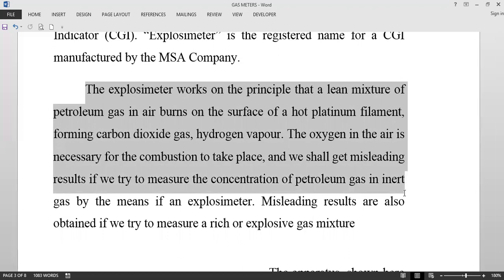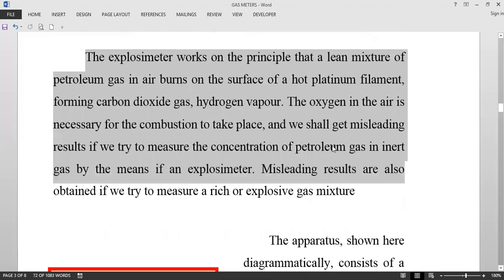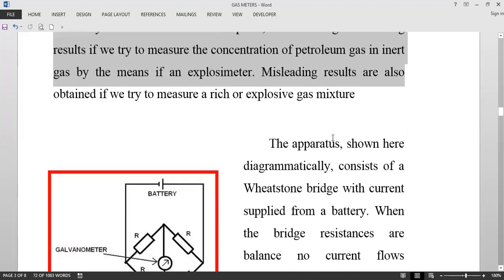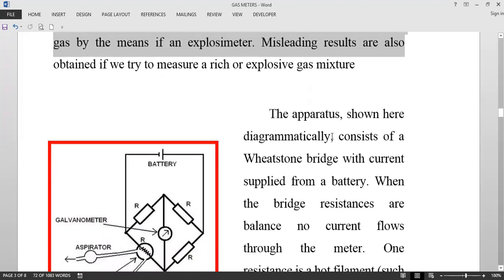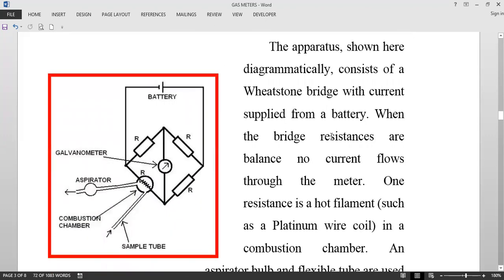We will get misleading results if we try to measure the concentration of petroleum gases in an inert condition by means of an explosimeter. We will also get misleading results if we try to measure a rich or explosive gas mixture. So it has to basically be used when the gas mixture is at very low concentrations.